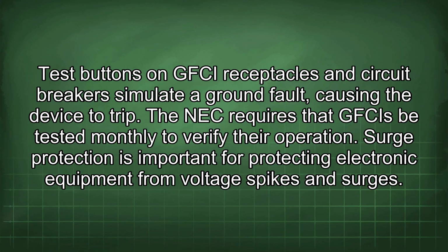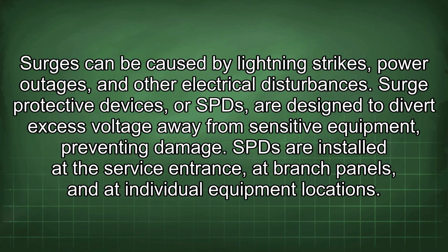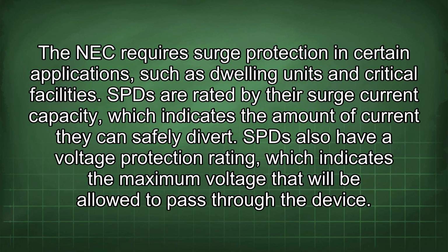Surge protection is important for protecting electronic equipment from voltage spikes and surges. Surges can be caused by lightning strikes, power outages, and other electrical disturbances. Surge protective devices, or SPDs, are designed to divert excess voltage away from sensitive equipment, preventing damage. SPDs are installed at the service entrance, at branch panels, and at individual equipment locations. The NEC requires surge protection in certain applications, such as dwelling units and critical facilities. SPDs are rated by the surge current capacity, which indicates the amount of current they can safely divert.